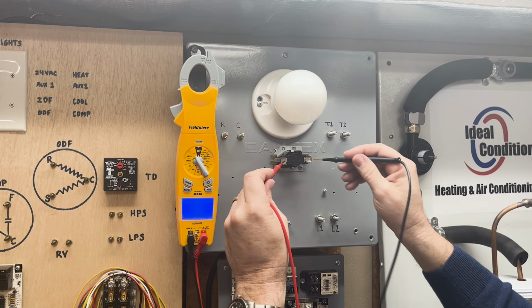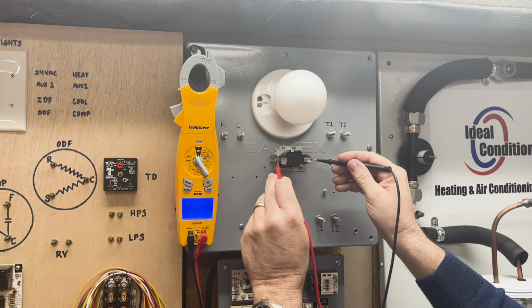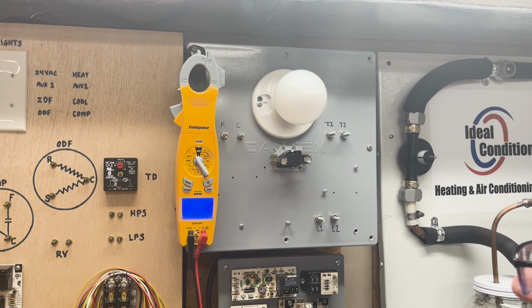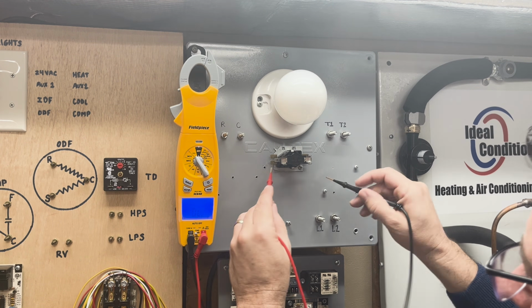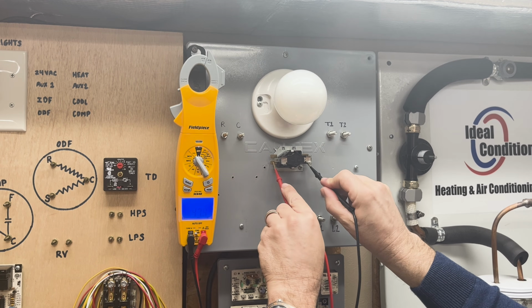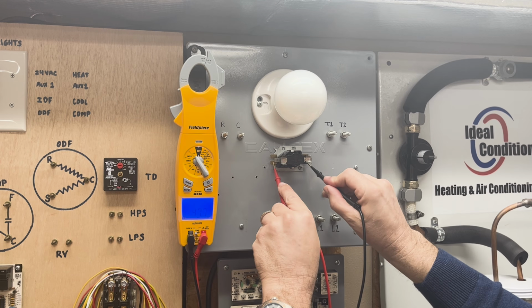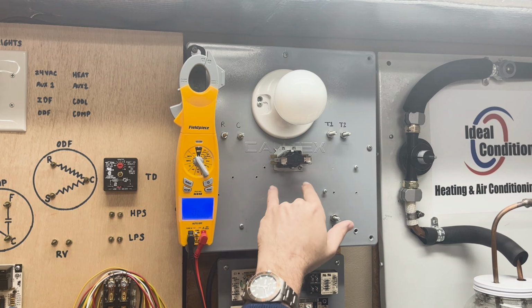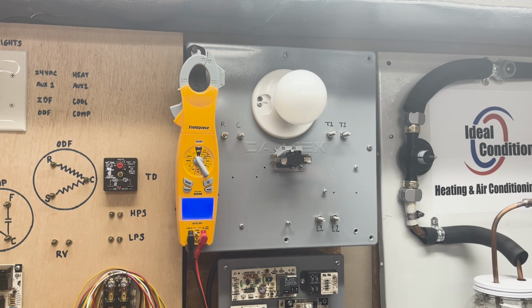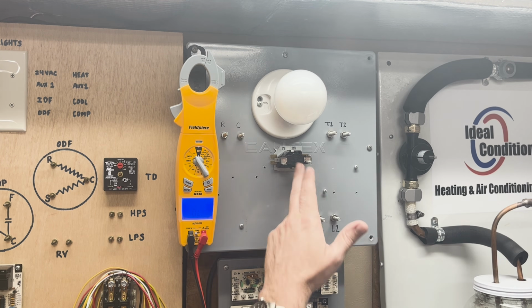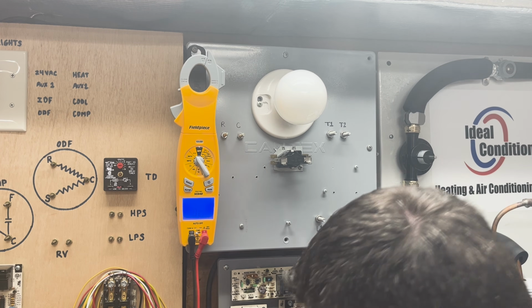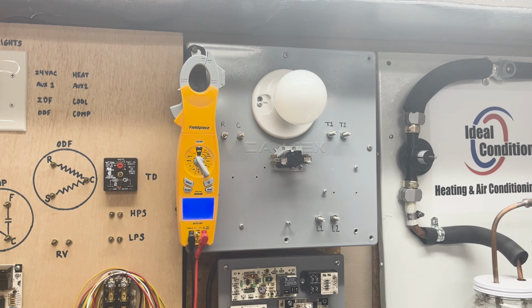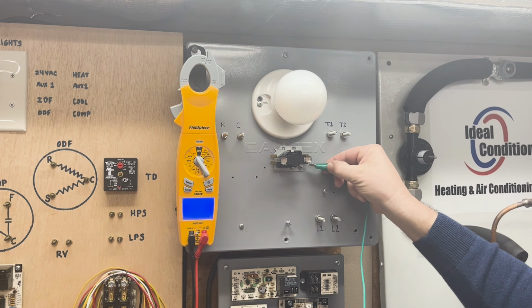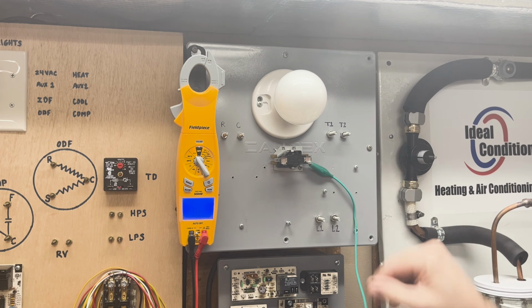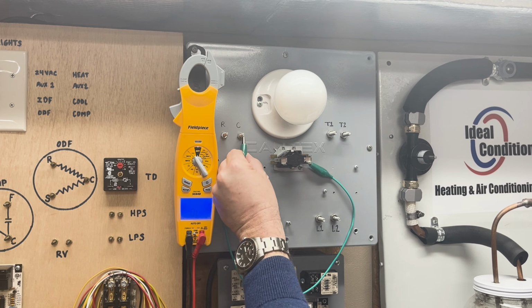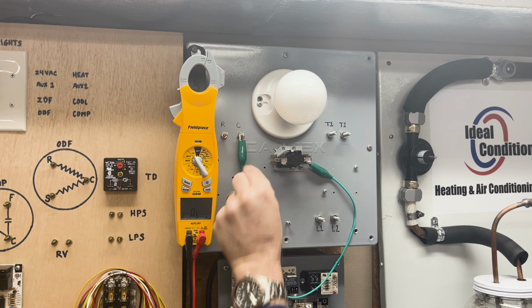That's how I would test this relay. Okay, the relay's not stuck closed. And then if I came over to here, down at the bottom, I should read numbers. And I'm reading 47.6. So I know that the resistance is a little higher on this. Once it warms up, it'll make contact. So now what I'm going to do is I'm going to take these two wires here, and I'm going to apply 24 volts to the bottom of this time delay relay.